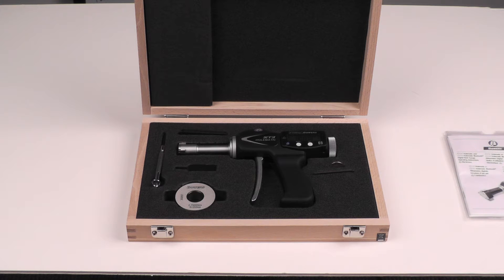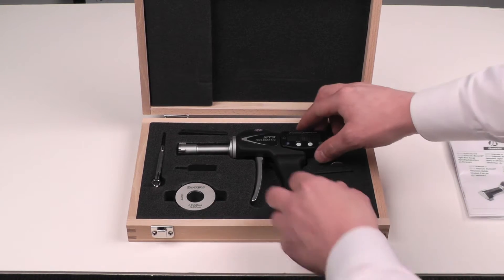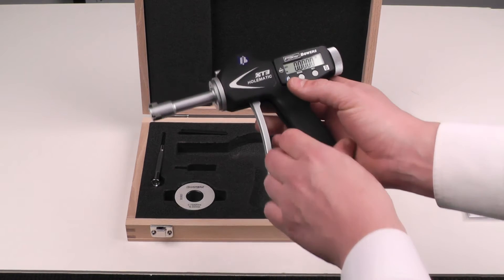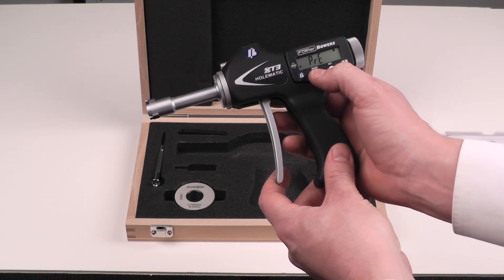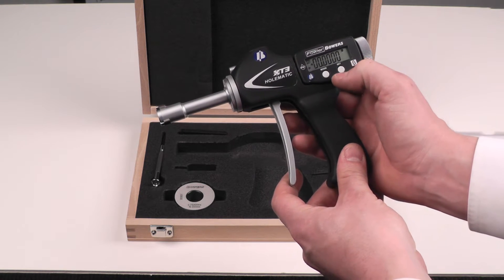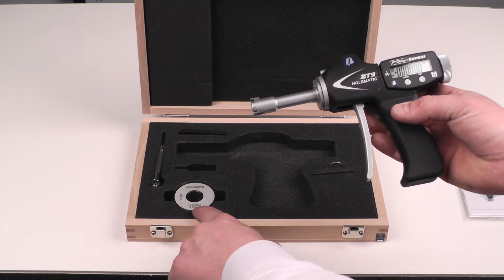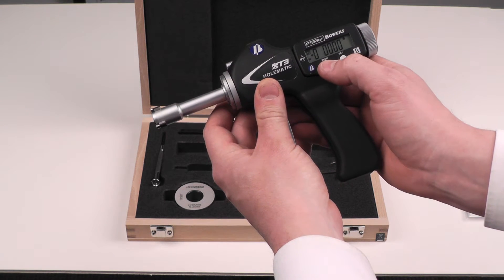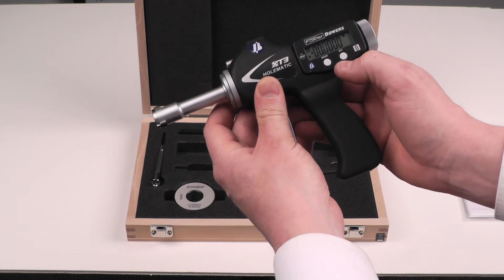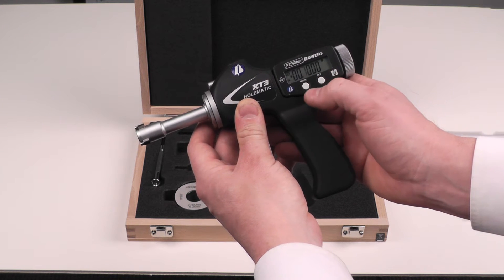The first step when you first unbox your Fowler Bowers XT3 Holematic Bore Gauge is to enter the size of the master ring into the electronics. Using the mode button — it'll take three presses — there's the preset function. Hit set and you will see the first digit blinking. Now we have a .75 inch ring and we are in inch mode, so using the mode button we will switch the active number to the first one we want to change. Quick presses of the set button will change that digit.